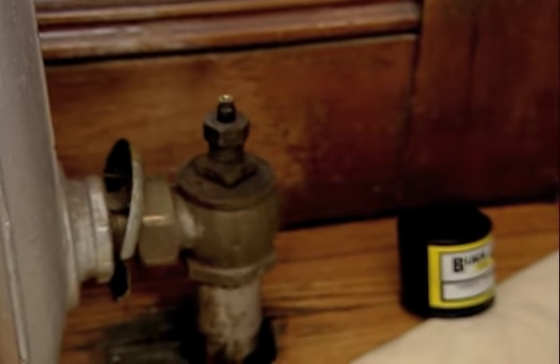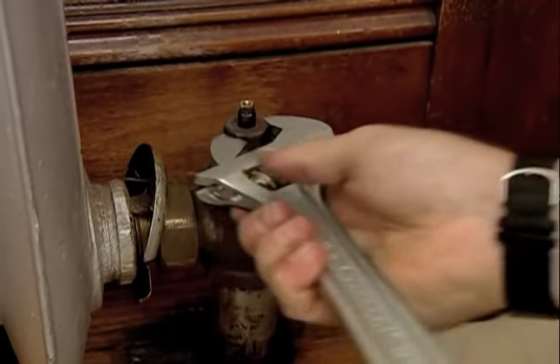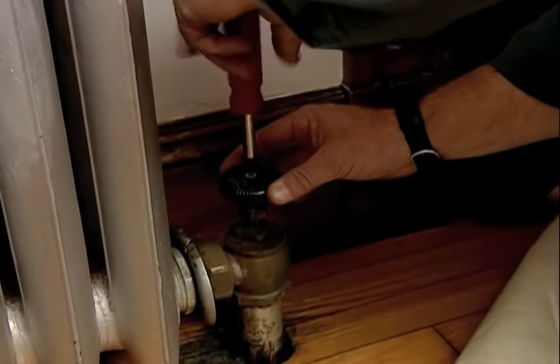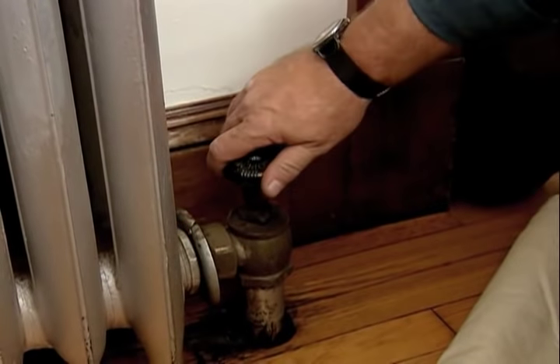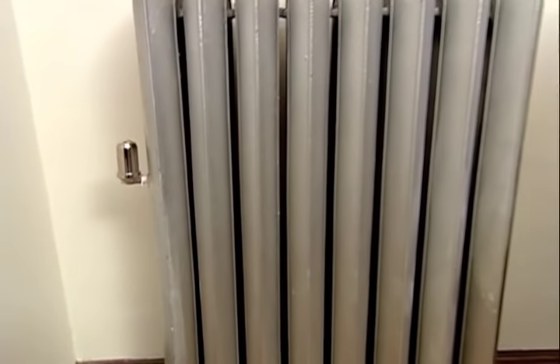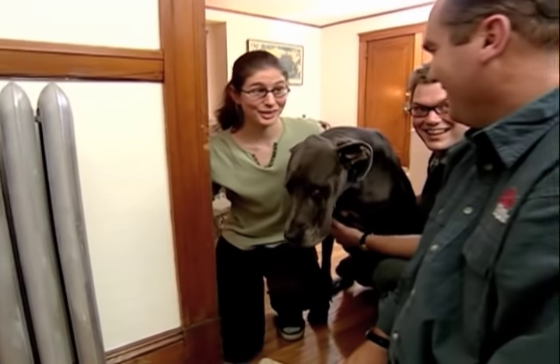While I'm doing that, why don't you turn the thermostat back up and let's crank it up and test it out. With the steam back up, let's see how we did. This guy's nice and tight, not a drop coming out there. And barely a little — I don't hear anything. And that's not a bad thing, is it? No, it's good.